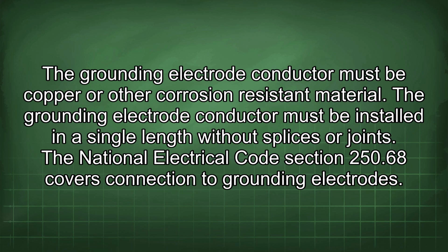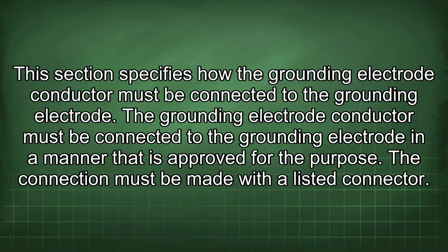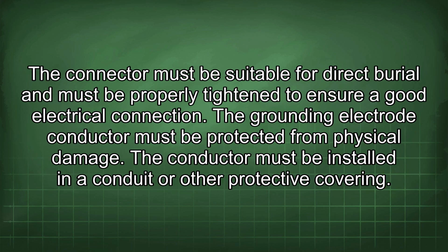The National Electrical Code Section 250.68 covers connection to grounding electrodes. This section specifies how the grounding electrode conductor must be connected to the grounding electrode. The grounding electrode conductor must be connected to the grounding electrode in a manner that is approved for the purpose. The connection must be made with a listed connector. The connector must be suitable for direct burial and must be properly tightened to ensure a good electrical connection. The grounding electrode conductor must be protected from physical damage. The conductor must be installed in a conduit or other protective covering.